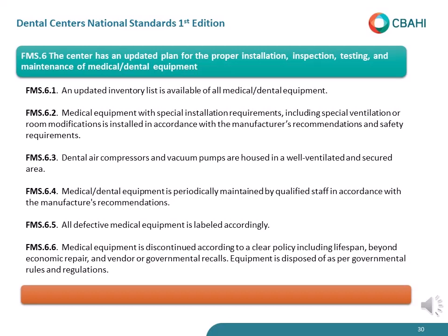6.3, dental air compressor and vacuum pumps are housed in a well-ventilated and secured area. The dental compressor is a medical air source, so it needs to be well housed and in a ventilated area so that you minimize the risk of it going out of order or something like that.